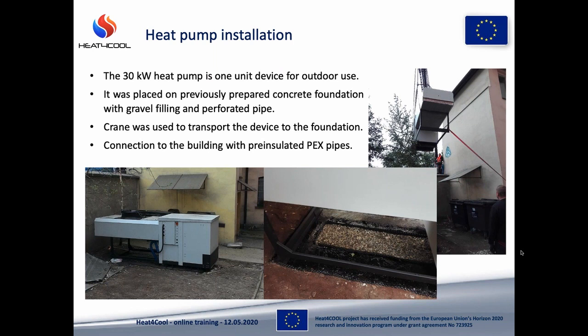The heart of the retrofitted system is the 30 kilowatt heat pump, which is a monoblock outside machine. The heat pump stands on the previously prepared foundation with gravel filling, which allows condensate to go to the sewage system, as inside the foundation there is a perforated pipe. The device was transported to the foundation using a crane, as the backyard of the building is a little lower than the rest of the terrain, and also there is a big mass of the heat pump.